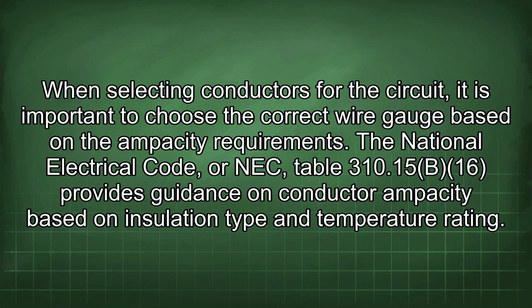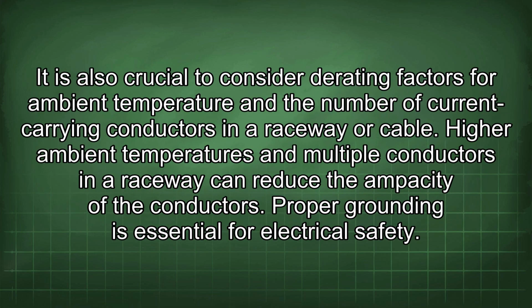failure. When selecting conductors for the circuit, it is important to choose the correct wire gauge based on the ampacity requirements. The National Electrical Code, or NEC, Table 310.15(B)(16) provides guidance on conductor ampacity based on insulation type and temperature rating. It is also crucial to consider derating factors for ambient temperature and the number of current carrying conductors in a raceway or cable. Higher ambient temperatures and multiple conductors in a raceway can reduce the ampacity of the conductors.